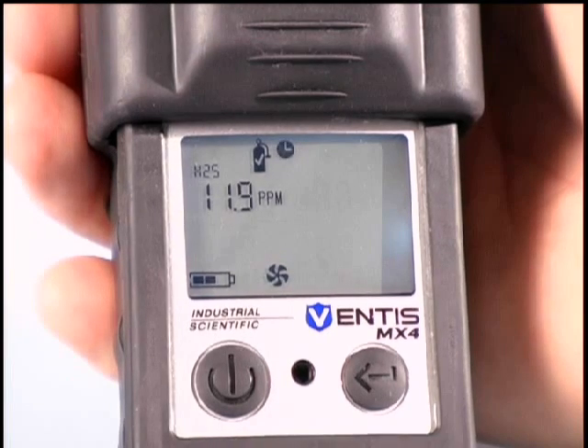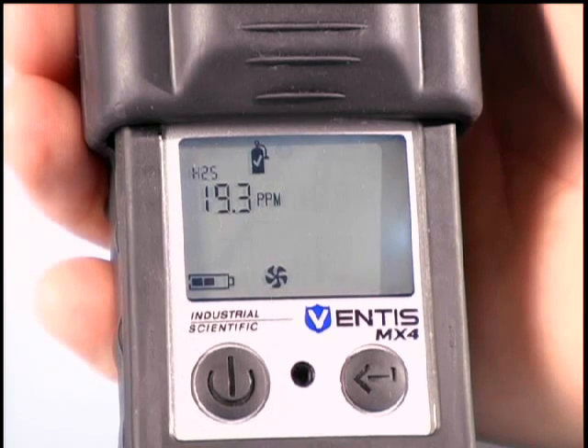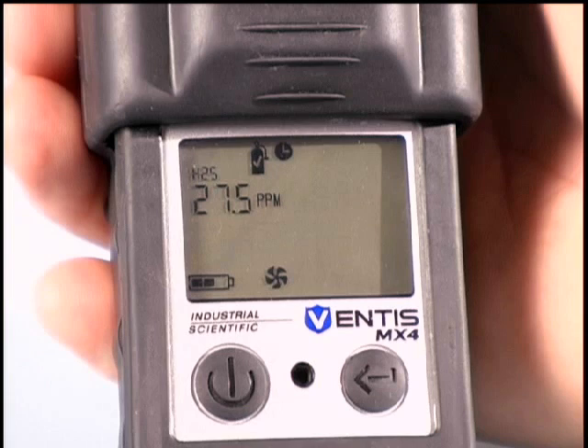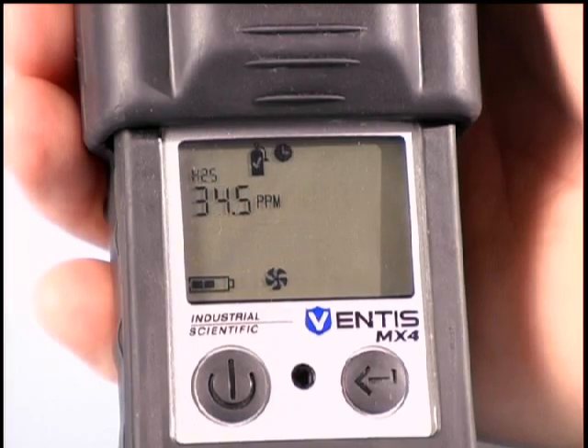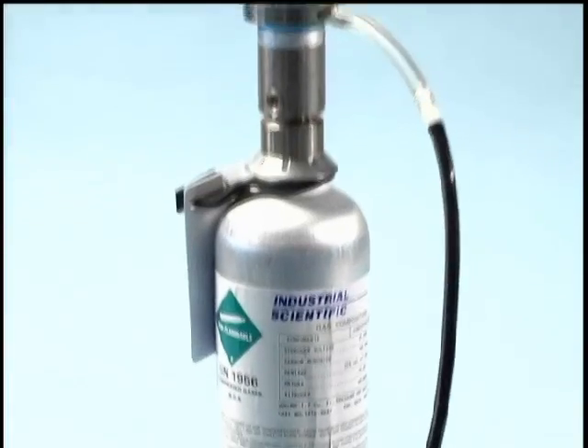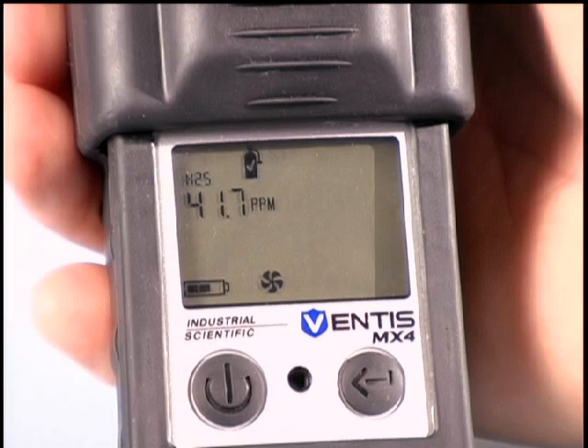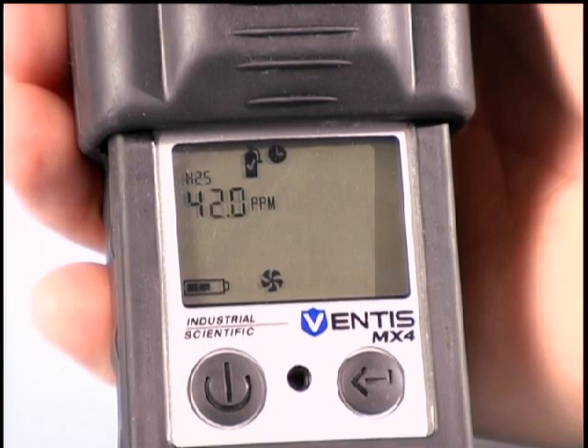The calibration process for Ventis MX4 is easy and automatic. The display will prompt you what gases to apply and at what time. To skip a specific sensor at any time during its calibration, just press the on-off mode button to go to the next sensor. If you choose to calibrate a sensor, apply the applicable gas with a demand flow regulator and correct diameter tubing for an aspirated configuration.